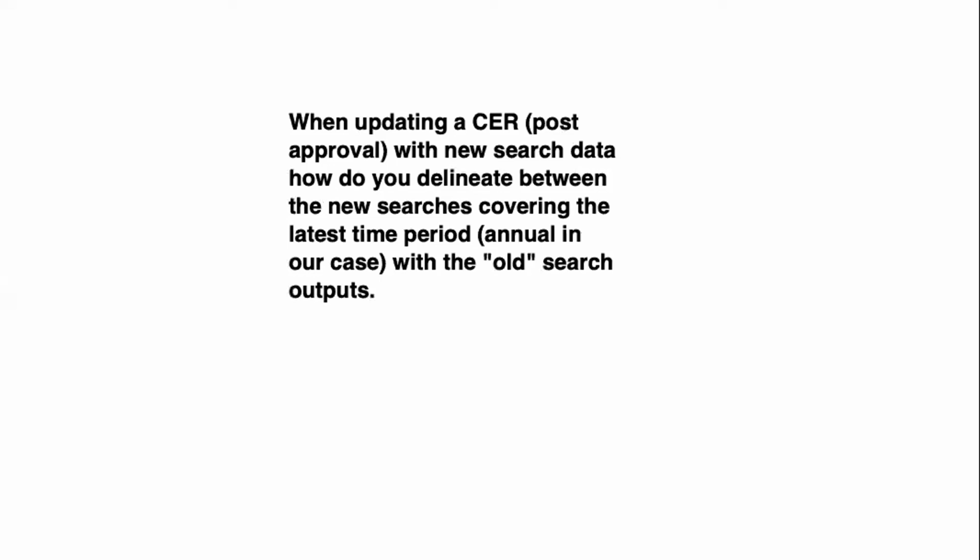If that's not the case, and we're just simply updating last year's CER, and its methodology was very good, we will do just a bridge search using the same methodology, the same search terms, and it might only be a year. And we'll use the old results, present them in the CER along with the new results, the included articles and included clinical data, and analyze that all together. You do have to do a total analysis, taking into consideration not only the old data, I use that with quotes, plus the new data that you just gleaned on a bridge search.